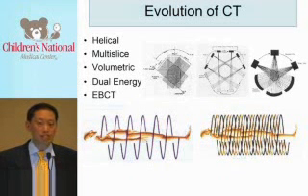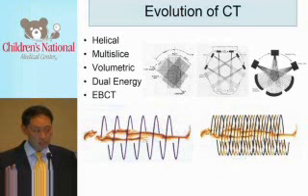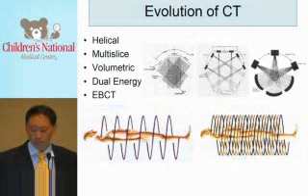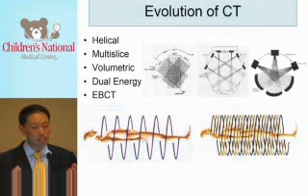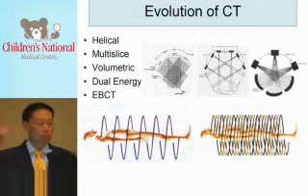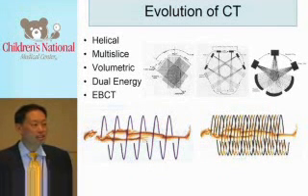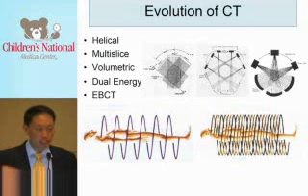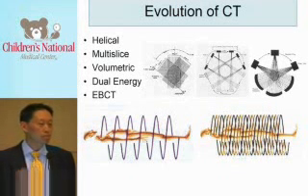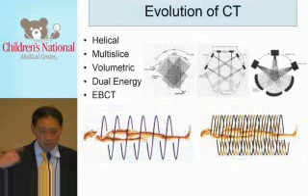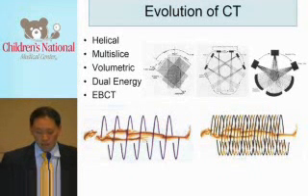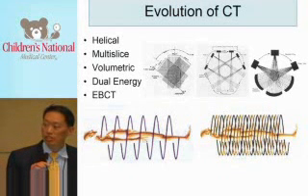Then someone came with the idea of decoupling the imaging source from the power source. It used to be on a tether or a leash. You'd have to hit it, unwind it back, scan, wind it back there. Slip ring technology allowed a continuous rotation because now the energy was supplied directly to the camera via the metal tube or housing, which was the birth of spiral or helical CT.